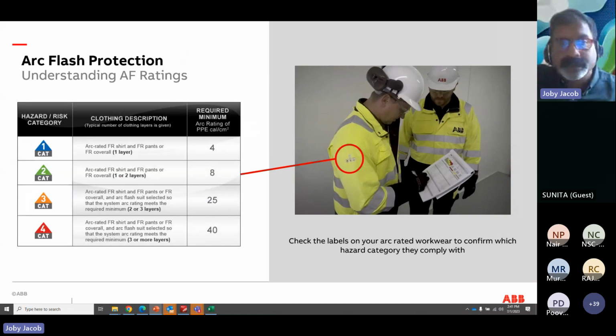We discussed various types of hazard category, Cat 1, Cat 2, Cat 3, and Cat 4. Cat 1 is up to 4 cals, Cat 2 up to 8 cals, Cat 3 25 cals, and you can attain it by layering also, not directly going for a Cat 3. So during the switching operations, you can have 8 cals plus 8 cals with the air gap, and you may get up to 25 cals. That's how the studies are calculated. So you don't need to wear the cumbersome 25 cals or 40 cals directly. If it is above 40 cals, you can have 25 cals plus 8 cals with the air gap, and you may get up to 40 cals. That's how we manage.